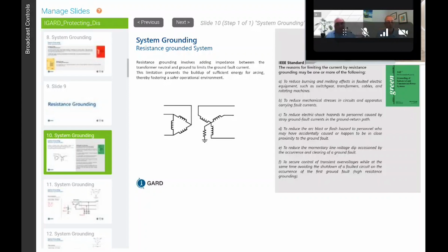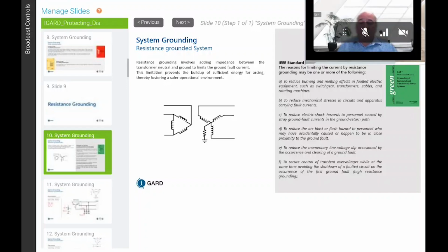So what are the reasons that we ground with a resistor? To reduce burning and melting effects in faulted electrical equipment, to reduce mechanical stresses, to reduce electric shock hazards, to reduce arc blast or flash hazards, to reduce the momentary line voltage dip that occurs when you have a ground fault, and to secure control of transient overvoltages while at the same time avoiding shutdowns.